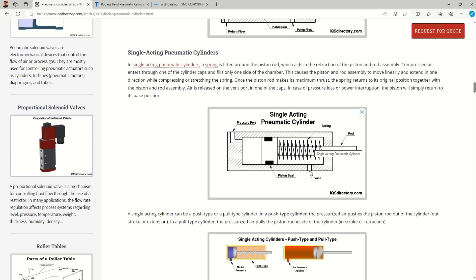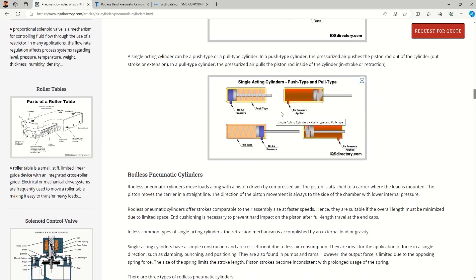Many people don't know that even a single acting cylinder has two ports. One is the pressure port and the other is a vent — a simple hole — because when you pass fluid on one side, the air from the spring side must exhaust, otherwise the spring cannot compress. There are two subtypes of single acting cylinders: push type and pull type, and when selecting a cylinder you must choose which one you need.